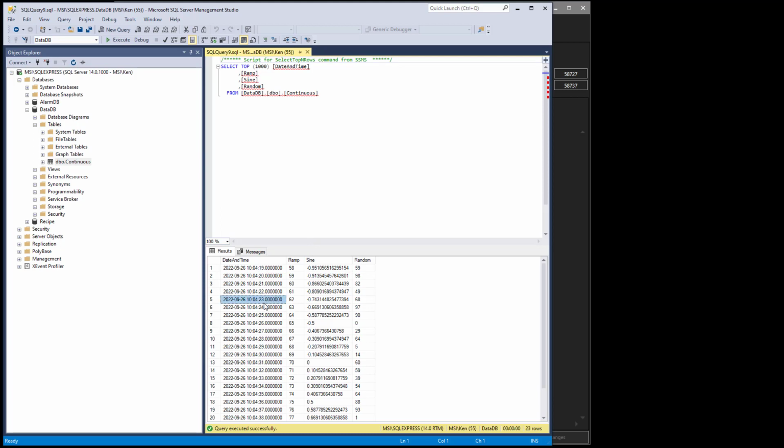Now the resolution that we have with the timestamps is down to 100 nanoseconds. And you're seeing the time logged here at the 1 second frequency because that's what we've specified to do. In a moment, we're going to dive into some of the other types like data change, and we'll see the time resolution come out to that. But with the 1 second frequency, we're indexing the values that we've received and we match it up: does it belong at this record or the next record, depending upon what time it needs to be recorded.